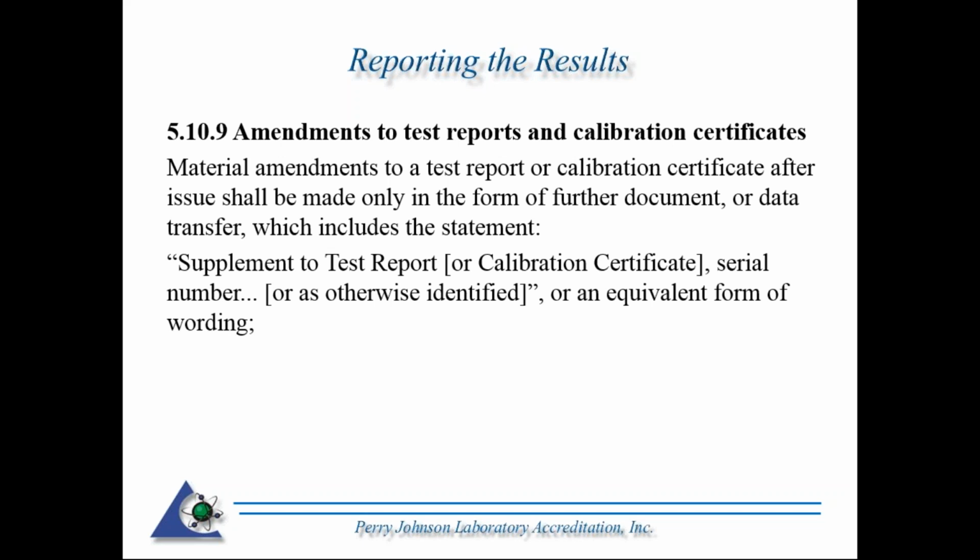Hence, if you issue a report, you need to add to the report, need to relay some further information regarding the test or calibration report. You're not going to issue a whole new report. You're going to issue a supplement. So it needs to be specified as a supplement. It needs to contain that unique identifier that the initial report has.